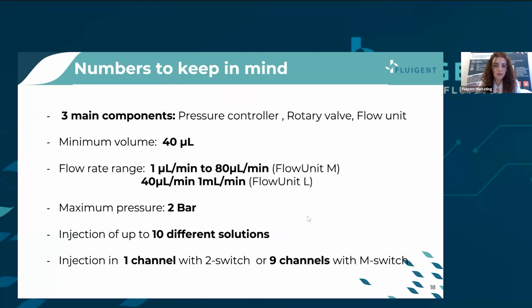So these are the numbers to keep in mind regarding the product. We have 3 main components: the pressure controller, the rotary valve, and the flow unit, in which we will monitor the flow rate that is being injected. The minimum volume required is 40 microliters, and the flow rate range is from 1 microliter per minute to 1 milliliter per minute, depending on the flow unit that we use. The maximum pressure is 2 bars, and we can inject up to 10 different solutions in one channel with the 2 switch, or 9 channels with the M switch.